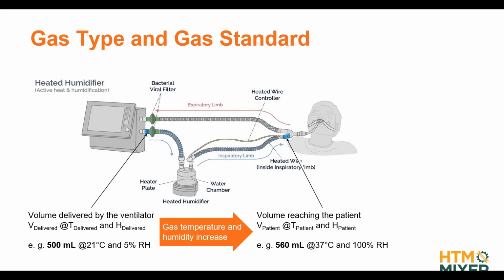So that means the volume that actually reaches the patient is no longer the 500 milliliters that the ventilator delivered to the circuit system. Considering that typically you want the temperature at 37 degrees Celsius, that's the typical body temperature, and about 100% humidified, our volume is going to be something around 560 milliliters, and not the 500 milliliters that the ventilator delivered to the circuit system. Because of that, what ventilator manufacturers typically do in their settings and monitoring is compensate for that. So typically you would see the setting on the ventilator is not the 500 milliliters that it delivers to the circuit system, but the 560 milliliters that are going to end up at the patient, right? And as we've learned earlier, that can all be calculated by gas standard conversion.